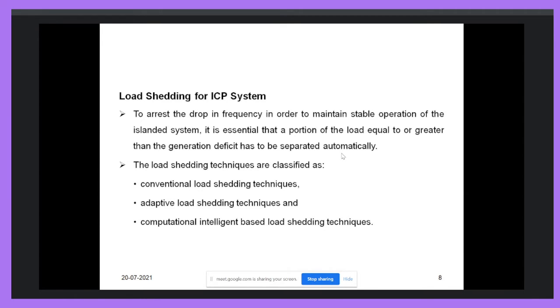Load shedding techniques can be classified as conventional, adaptive, and computational intelligence based load shedding techniques. In conventional load shedding, we can use different techniques like frequency based load shedding, breaker interlock load shedding, and PLC based load shedding. In adaptive load shedding, we can use a df/dt relay. The rate of change of frequency relay can be used to disconnect the load, and this scheme comes under the adaptive load shedding scheme.